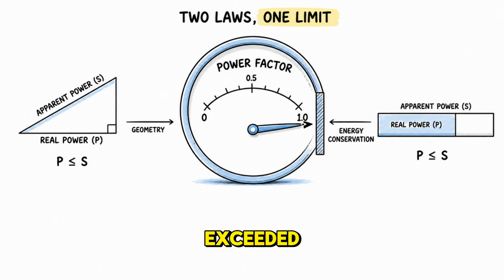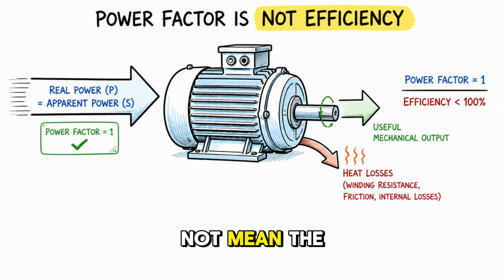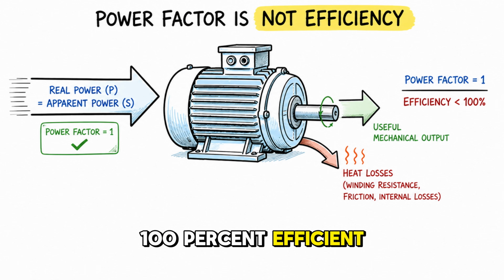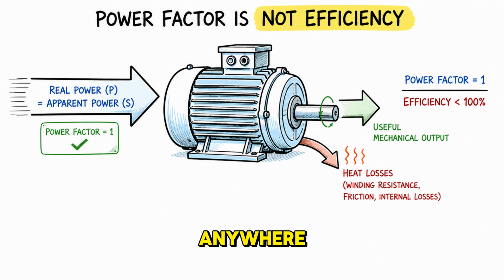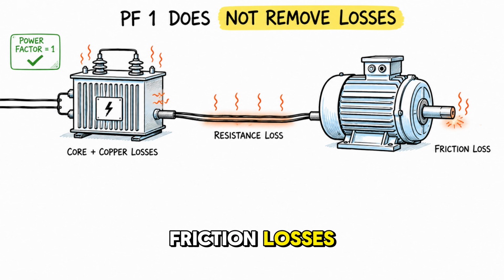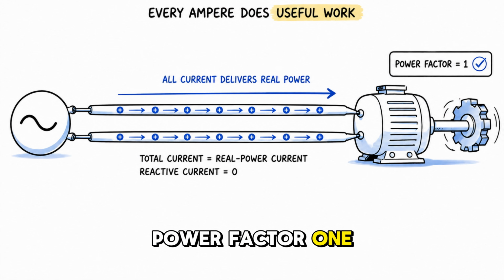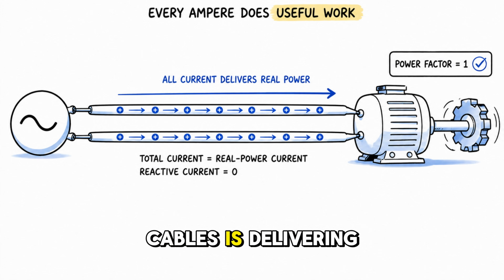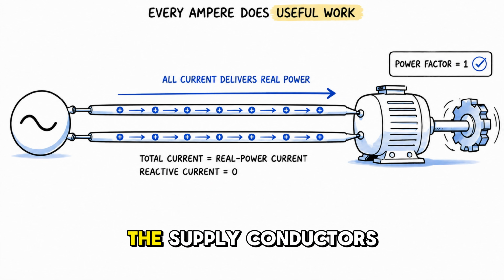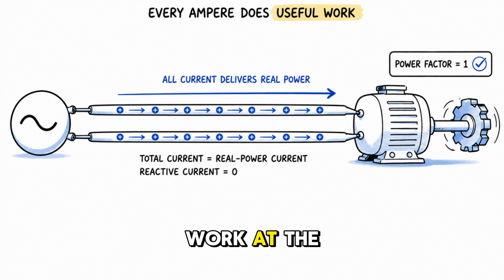It cannot be exceeded. Power factor 1 does not mean the installation is 100% efficient, in the sense that no energy is wasted anywhere. Motors still have friction losses. Cables still have resistance losses. Transformers still have core and copper losses. Power factor 1 simply means that every ampere of current flowing through the supply cables is delivering real useful power. None of the current is reactive. None of it is bouncing back and forth doing nothing. Every electron that moves through the supply conductors is doing useful work at the load.